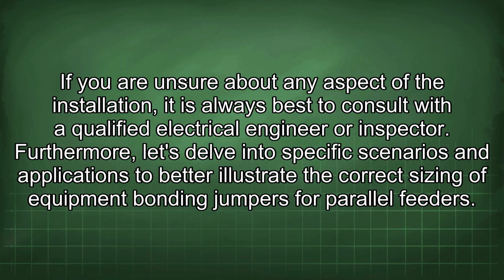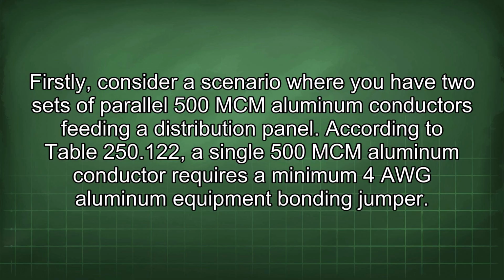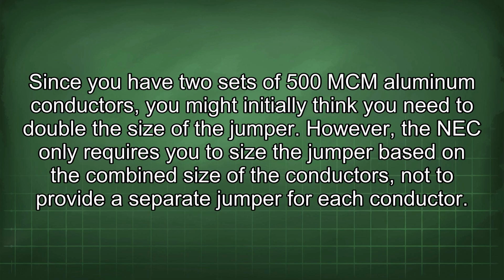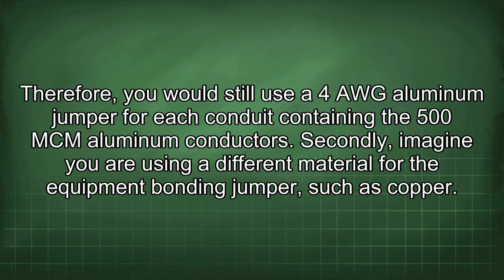engineer or inspector. Furthermore, let's delve into specific scenarios and applications to better illustrate the correct sizing of equipment bonding jumpers for parallel feeders. Firstly, consider a scenario where you have two sets of parallel 500 mcm aluminum conductors feeding a distribution panel. According to Table 250.122, a single 500 mcm aluminum conductor requires a minimum 4 AWG aluminum equipment bonding jumper. Since you have two sets of 500 mcm aluminum conductors, you might initially think you need to double the size of the jumper. However, the NEC only requires you to size the jumper based on the combined size of the conductors, not to provide a separate jumper for each conductor. Therefore, you would still use a 4 AWG aluminum jumper for each conduit containing the 500 mcm aluminum conductors.